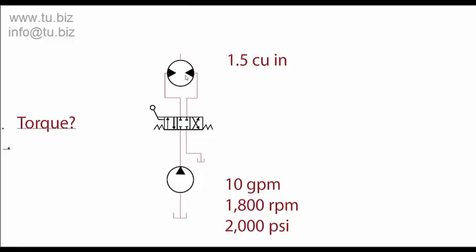So the formula is 2,000 psi times the displacement of the motor in cubic inches—1.5—divided by 6.28. That will give us the torque in inch-pounds.